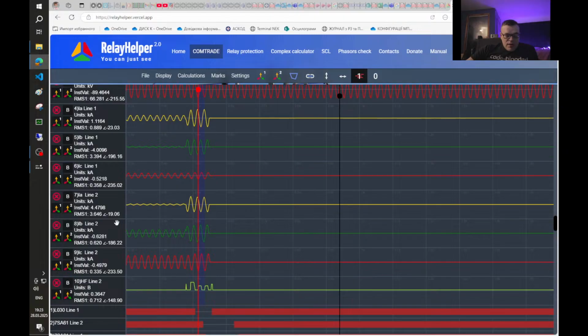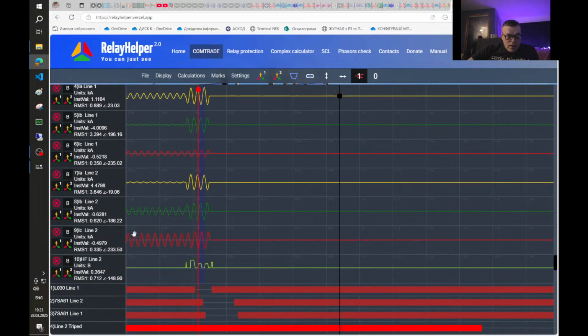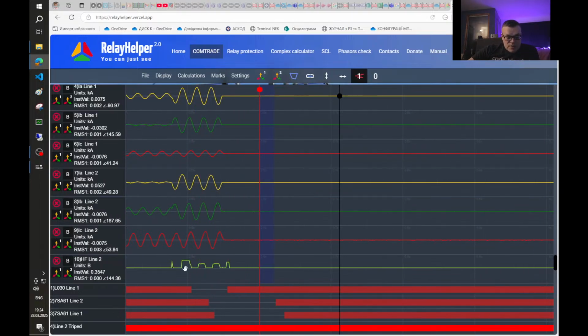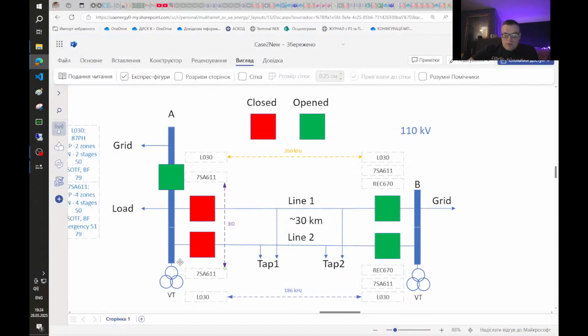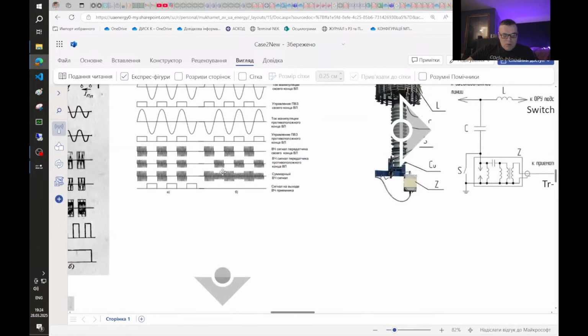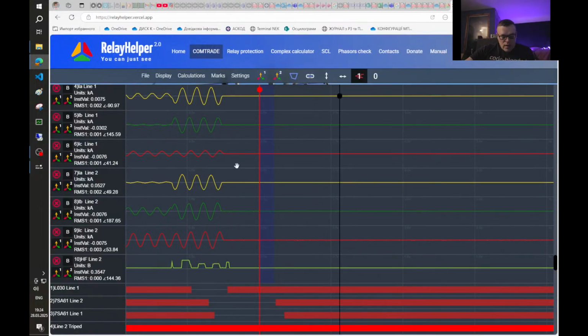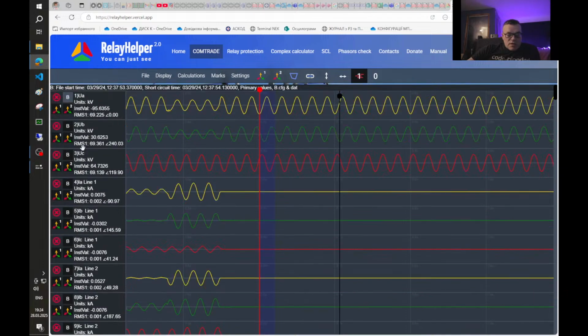The first strange thing is that on the first line the current increased a lot in phase B, but on the second line the current increased on phase A. Also, here you can see the high frequency signal and the pulses. For an external fault, the signal will look like that. And if we look at the voltages, we can see that the voltages in phases A and B decreased.